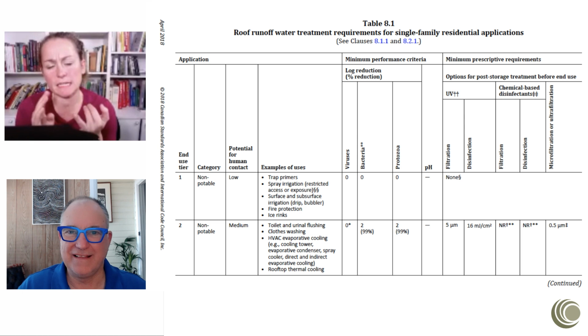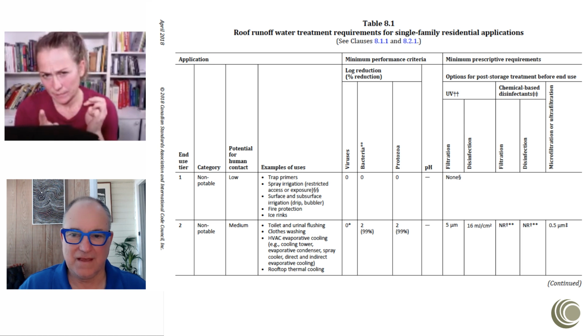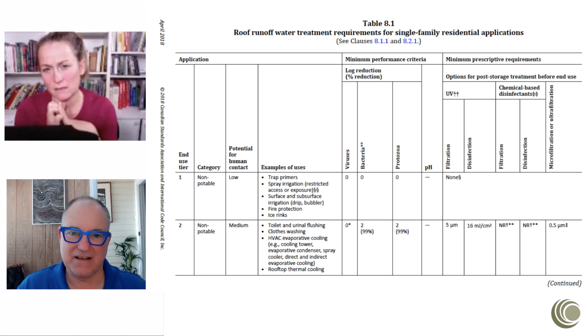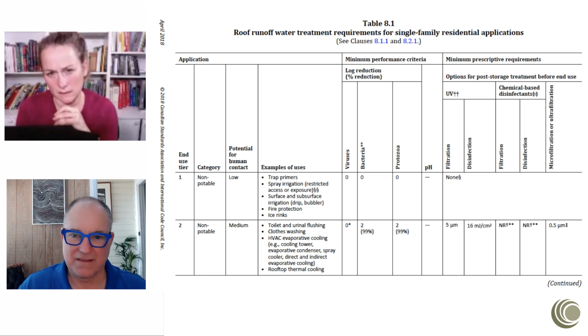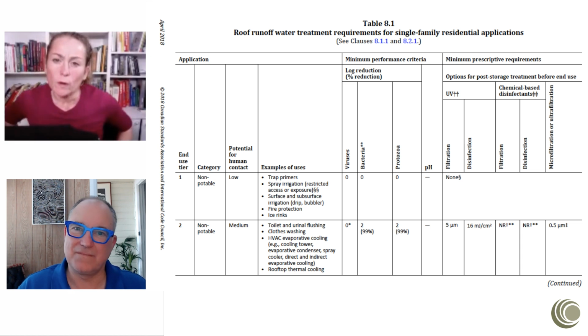So if there's viruses and bacteria, no, and here's where you're going to correct me. Legionella, which you mentioned earlier, is a bacteria. So what this standard is about, it's a really good point, Michelle, because if you're concerned about chemical or metals or other physical contamination of rainwater systems, there's nothing here that will actually make any difference. UV, chlorination, or ozone will not actually change that issue at all.